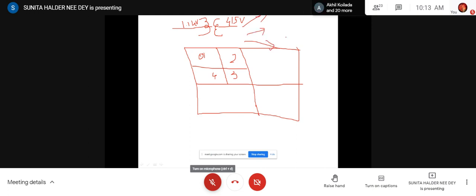have estimated right now. Now the load you have calculated, that is the connected load. So that is actually the possible maximum load in each sub-block. But every time all the loads are not connected. Some of them are always connected. So that's why the concept of demand factor has come. Demand factor means maximum demand by connected load. So that means what may be the maximum demand, that is important.